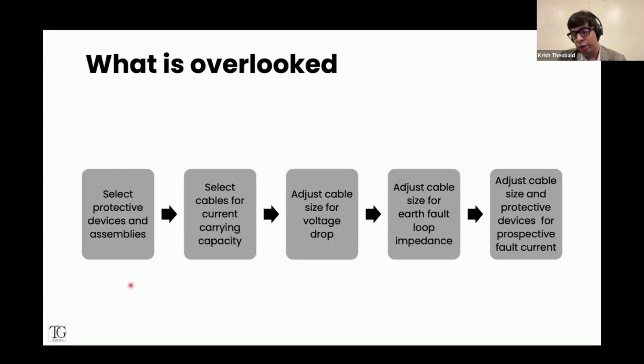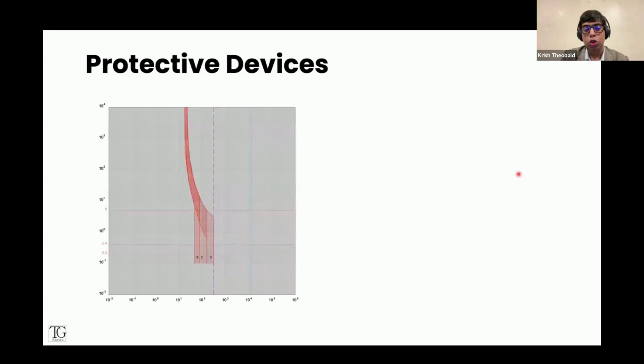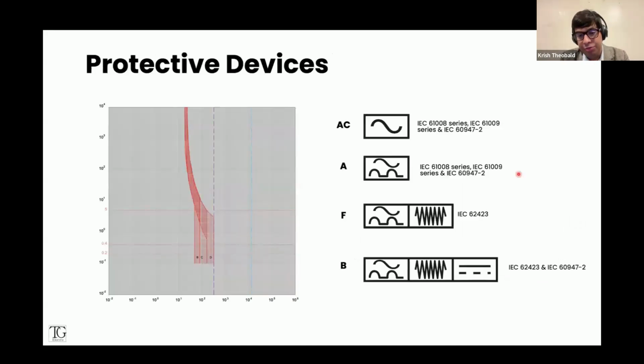Voltage drop, yeah, we do it, but how exactly do we do it? Let's look at it. Earth fault loop impedance, we don't really do, unfortunately. And those that measure earth fault loop impedance measure it after the installation is erected, and then you can't really do too much once the cables are already installed. And obviously, we do talk about protective devices for prospective fault current and short circuit current, but cables we don't really think about so much. So, what are our protective devices?